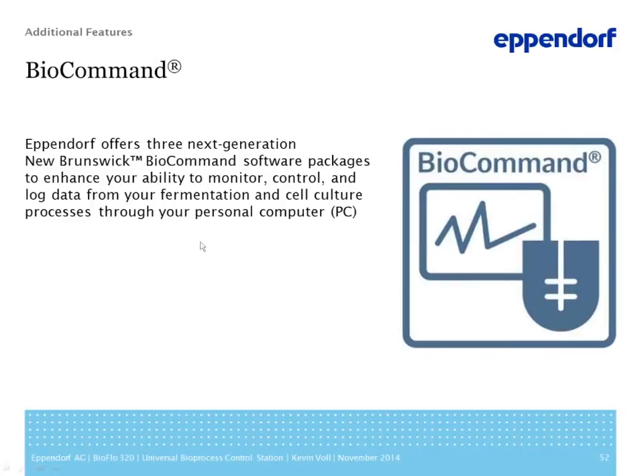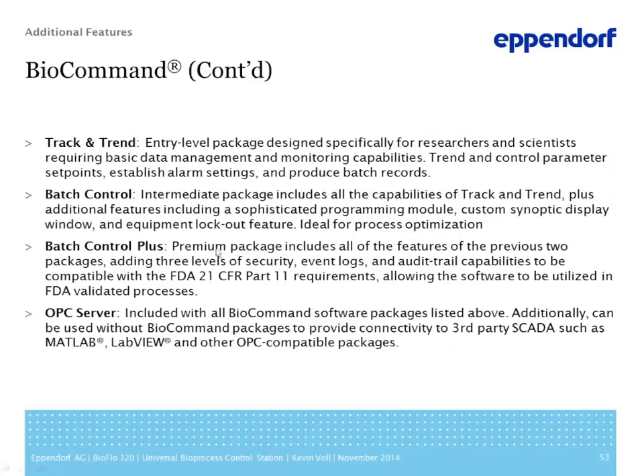BioCommand. So BioCommand is our supervisory control and data acquisition program from New Brunswick. BioCommand is offered in the same levels that it's offered today, and now this system is just able to communicate with BioCommand through Ethernet. So it's really just the difference in communication to the SCADA systems, not a difference in SCADA. So the niceties and the simple control strategies, the icon-based block programming with BioCommand, still available, and so the 320 can be directly integrated into any existing lab space that's using that today.